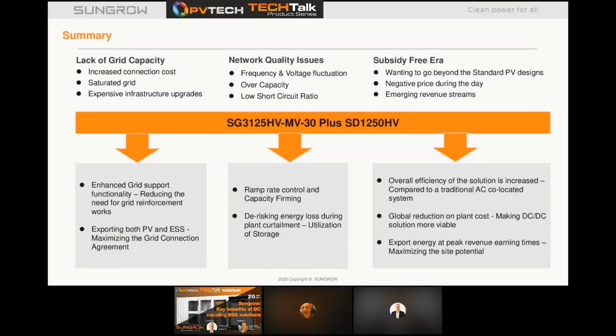So to summarize, the SG3125HV-MV DC-30 and the SD1250HV DC-coupled solution is able to bring in enhanced grid support functionality to ease expensive infrastructure upgrades, smooth the flow of energy into the grid by providing ramp rate control, store energy during times of curtailment for use at a later stage, bring savings to the build and its operation by reducing the balance of plant. Global reduction on plant costs is making DC-DC solutions more viable.